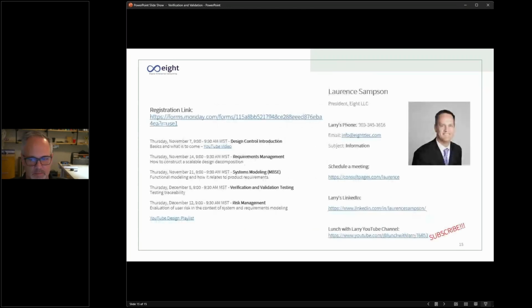So that really concludes the discussion for today. We're at about 27 minutes. I did have one question about why we should bother connecting output revisions to requirements. And really, it's because the DMR is the V&V evidence of the shipment. We want a report that shows that the DMR associated with what we're trying to approve for shipment is associated with those different requirements. How they're associated, what revisions, and do we have the appropriate amount of testing?